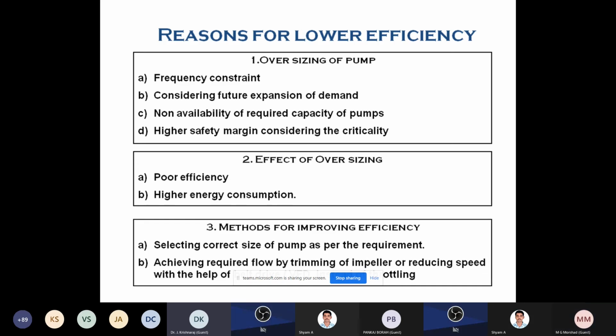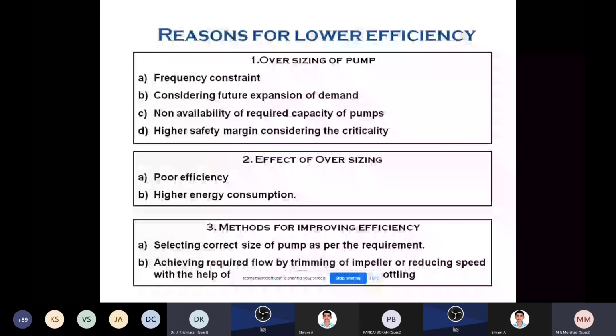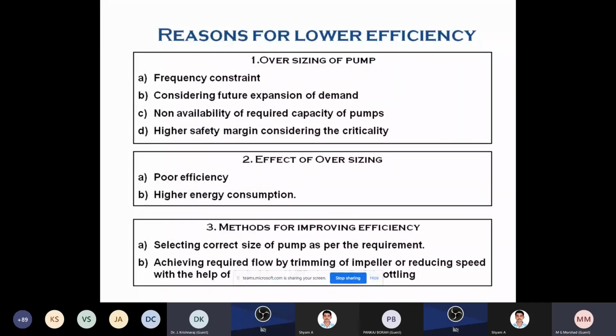The reason for the poor efficiency of the pump is that most pumps are oversized, because of the frequency constraint. Nowadays, for the last 20 years, the frequency variation is not there. But previously, before the power grid takeover, the frequency variation was there. So the manufacturer used to recommend a higher size pump, so that the flow remains higher whenever the frequency goes down for the centrifugal pump. Once oversizing is there, poor efficiency will also be there. So these are the basic reasons you have to find out and give the right recommendations.